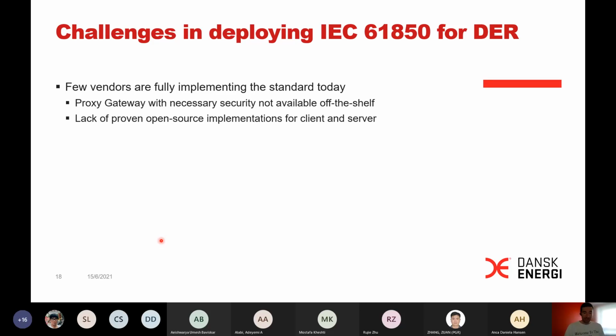The proxy gateway component, which should collect data from many units and send it onward, is a function that's common inside a station when you have many breakers and measurement units and want a single gateway or port to communicate through. But in this case of having a wide area network collecting data across a large geography and needing a proxy, there isn't an off-the-shelf product ready for that functionality. What's different is the security, especially needing authentication and encryption of every single link you're aggregating, and the need for automating all the handling of encryption keys and such.